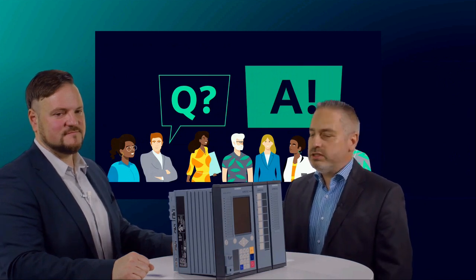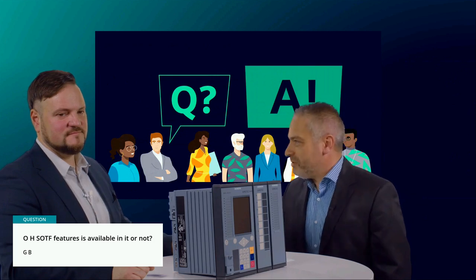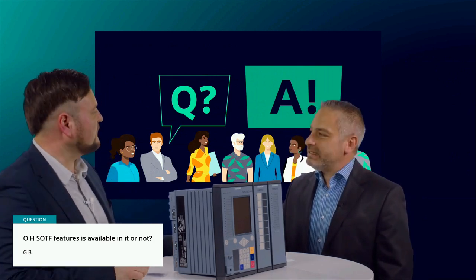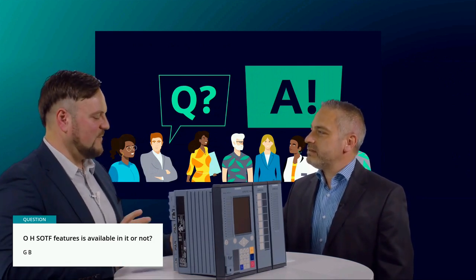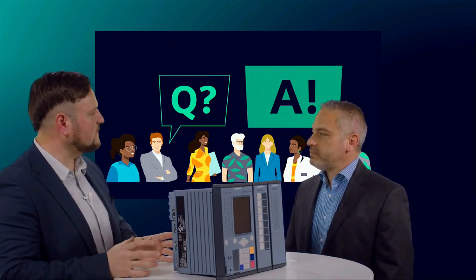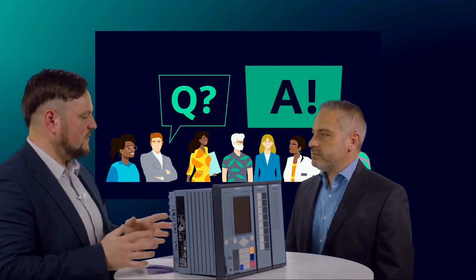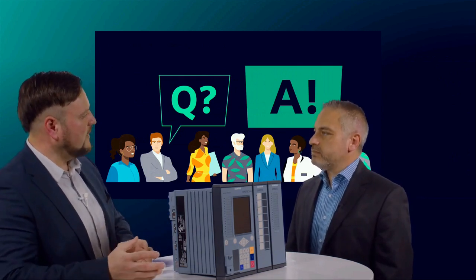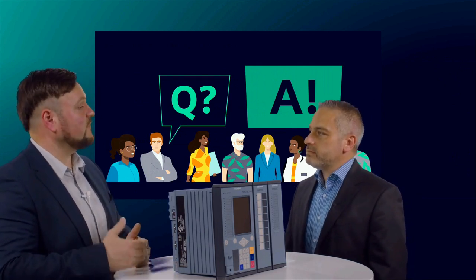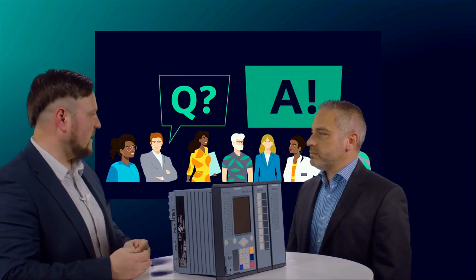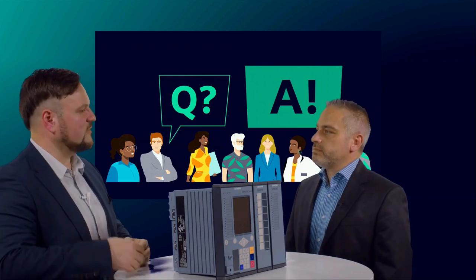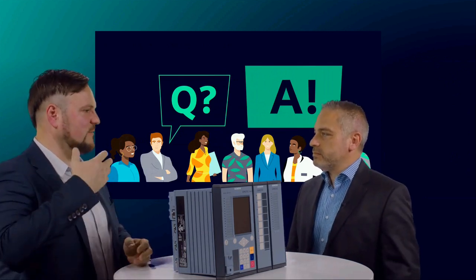Are there any soft features available in the 7UT85 or not? What does it mean, soft features? Everything is based on software. The HSBT functionality is implemented in the SIPROTEC 5 architecture, meaning you implement this functionality in a function group circuit breaker. You have predefined start types, and also the possibility to implement additional start types. For example, you want to start your transfer with reverse power protection, under voltage, or some other protection function. You can combine these. This is one of the advantages of the SIPROTEC 5 platform: you can combine everything and create new functionalities and new triggers to transfer your motor load.